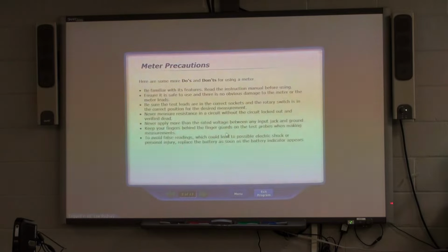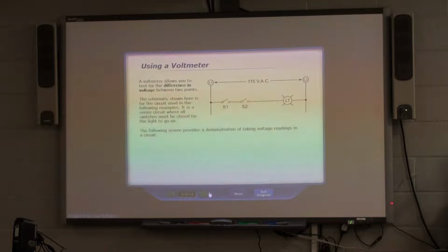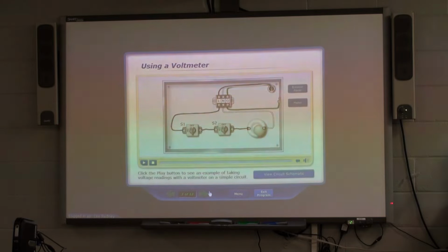Keep your fingers behind the finger guards on the test probes. If you notice on a test probe, there's a wide part of the test probe. That's a barrier for your hands. That's as close as you should be when you're measuring voltage with this thing. Never apply more than rated voltage to the input jacks. And to avoid false readings, replace the battery. A lot of meters will function with the battery indicator on, but they'll give you some wonky outputs. Not all will, it also depends on the state of that battery, but you'll start getting some flaky outputs. So I think you already know how to use a voltmeter and how to read it, and here we're going to see what they recommend.